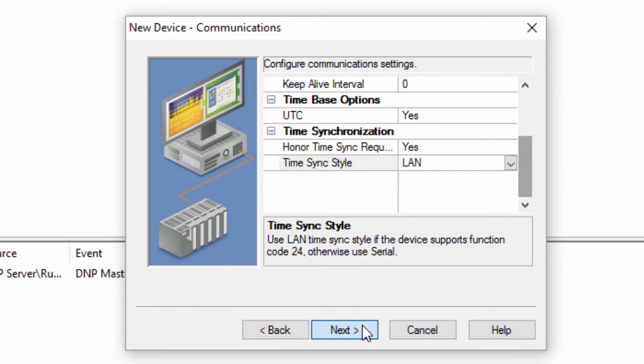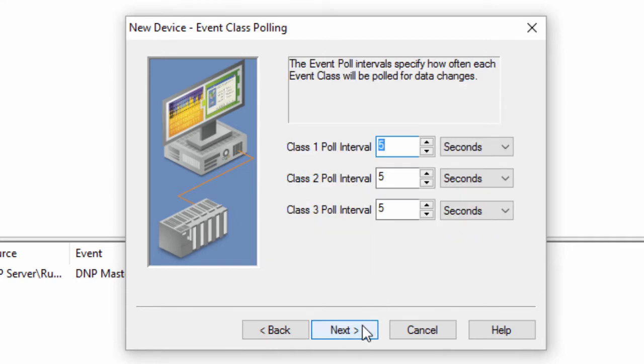Click Next to specify how often each event class will be polled for data changes. DNP has different event classes that you may use to classify points. You may set each of these to a maximum of 24 hours or set it to zero to turn off event polls.